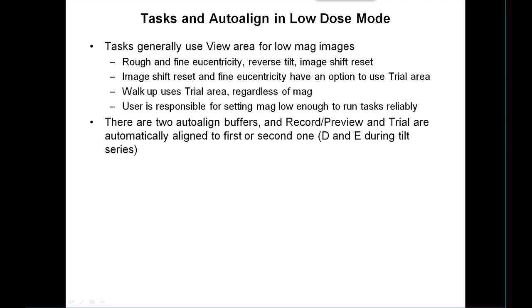Tasks work differently in low-dose mode because they generally use the view area instead of going down to their own preferred magnification. That applies to rough and fine eucentricity, the reverse tilt operation, and the image shift reset operation. Both image shift reset and fine eucentricity have an option to use the trial area instead, which some people want to do to keep as much dose as possible off the record area by avoiding the view. Walk-up uses the trial area regardless of mag, since we're going to be in a tilt series using the trial area to track as we tilt down, so we should be walking up with that as well.